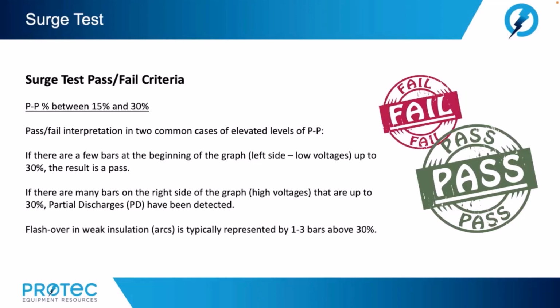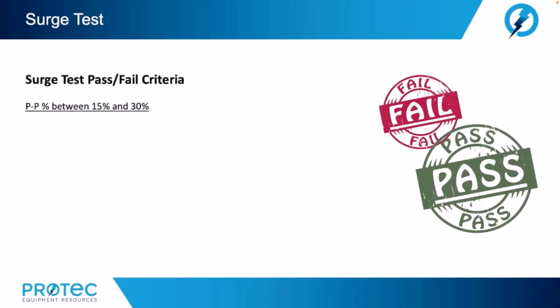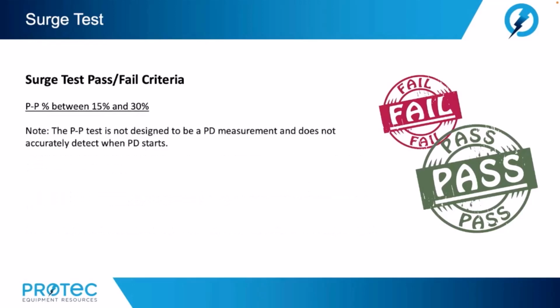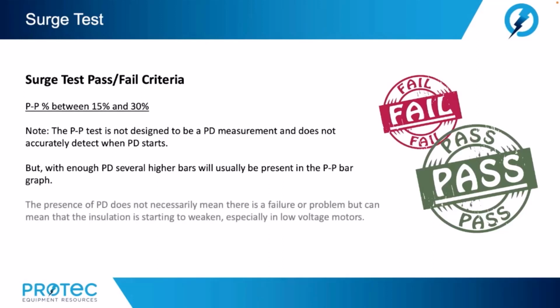Flashover in weak insulation, arcs, is typically represented by 1 to 3 bars above 30%. Note, the P2P test is not designed to be a partial discharge measurement and does not accurately detect when partial discharge starts. But with enough PD, several higher bars will usually be present in the P2P bar graph.